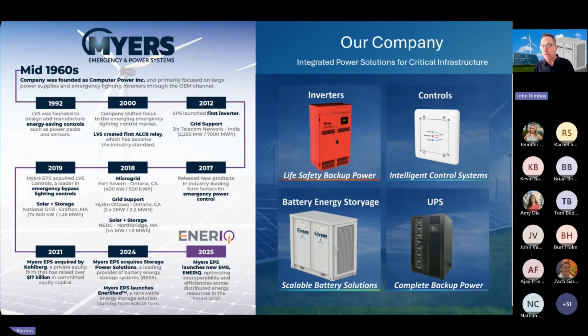In life safety, you have to have ventilation backed up within 60 seconds of a utility power break. So loads such as ventilation—like exhaust fans in a data center—or building access systems like automated doors, key card readers, facial recognition, or even turnstiles in large buildings, all need to be backed up. We can do that with an inverter, which is essentially batteries in a box with intelligence that hooks into your system.